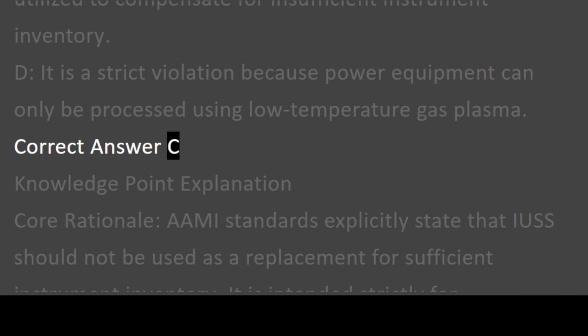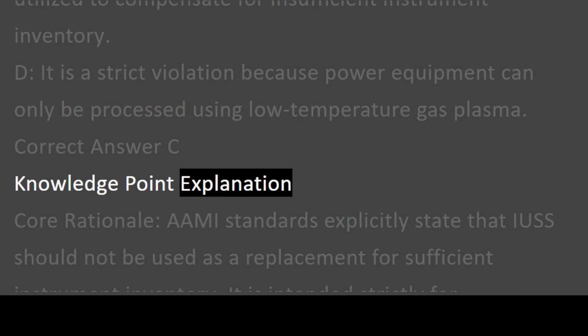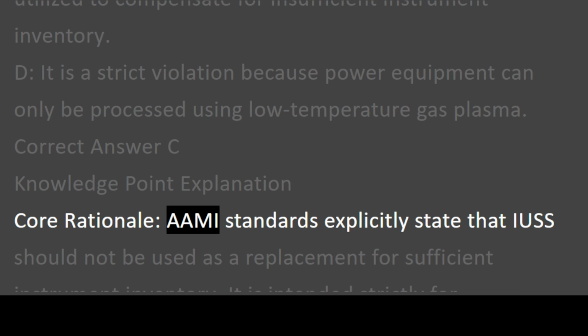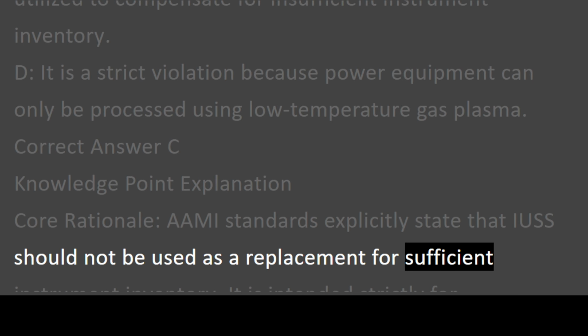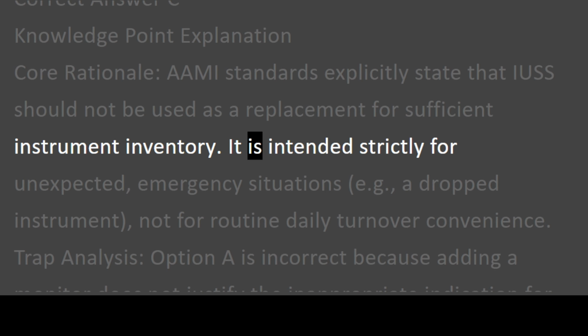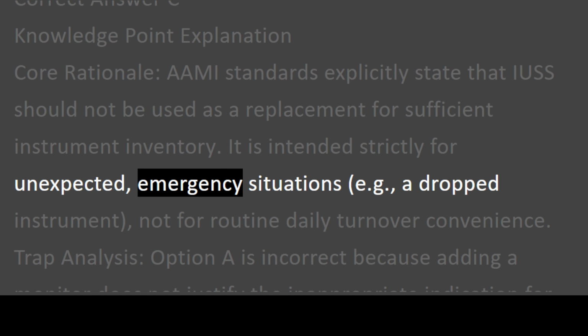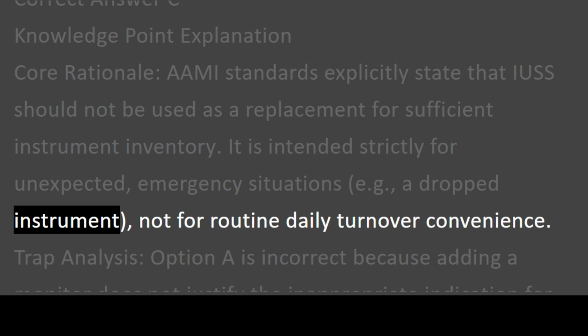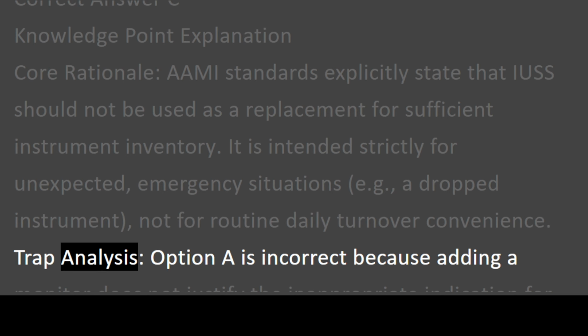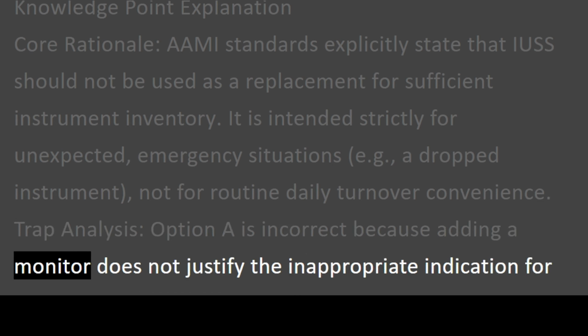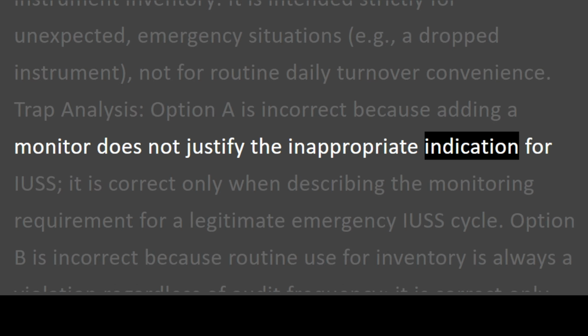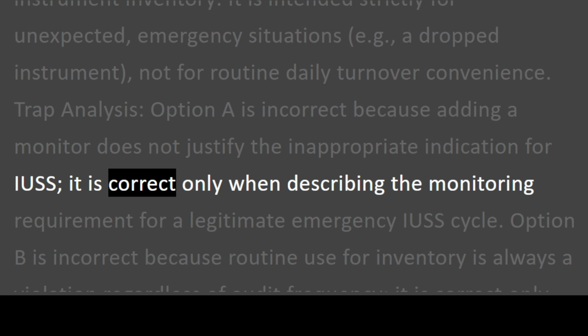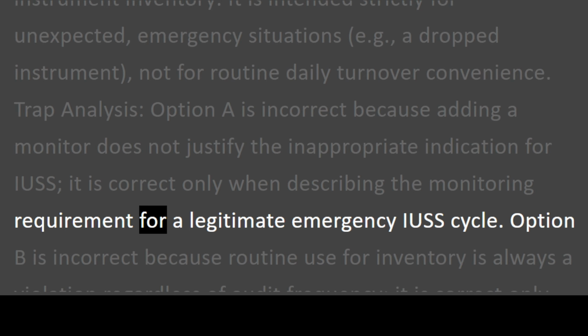Correct answer C. Knowledge point explanation. Core rationale. AAMI standards explicitly state that IUSS should not be used as a replacement for sufficient instrument inventory. It is intended strictly for unexpected, emergency situations, e.g., a dropped instrument, not for routine daily turnover convenience. Trap analysis. Option A is incorrect because adding a monitor does not justify the inappropriate indication for IUSS. It is correct only when describing the monitoring requirement for a legitimate emergency IUSS cycle.